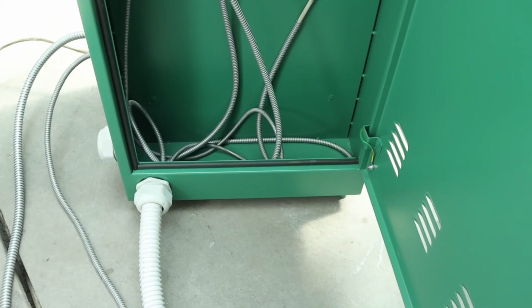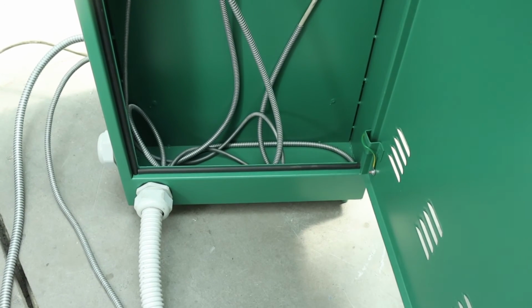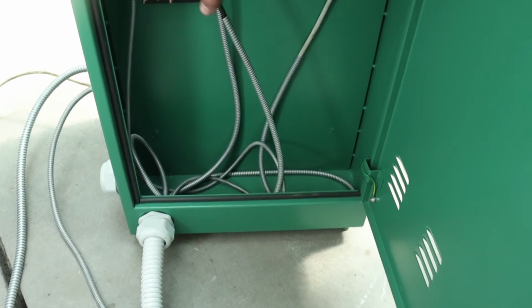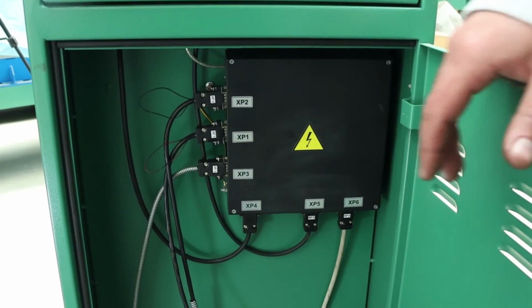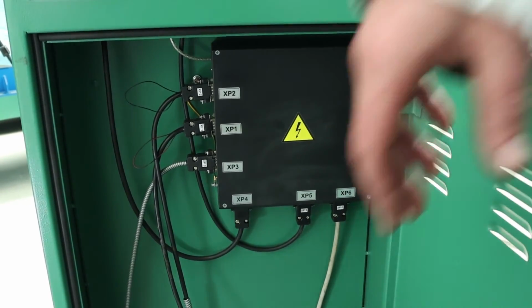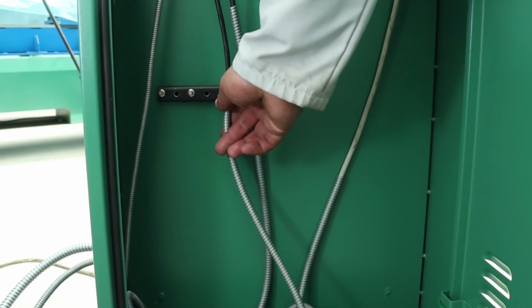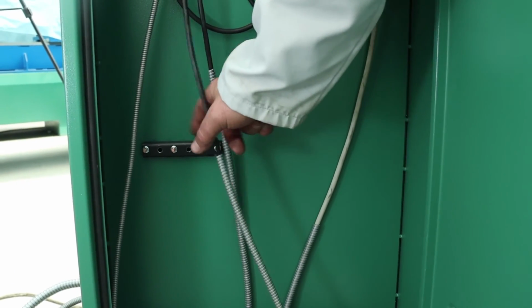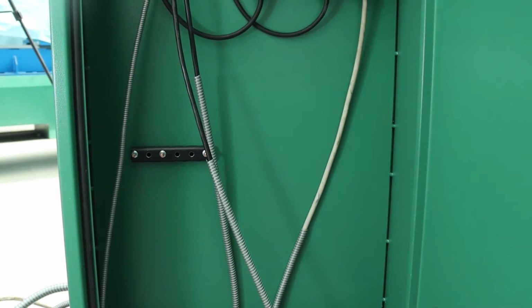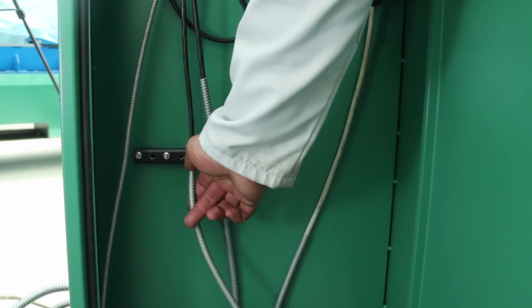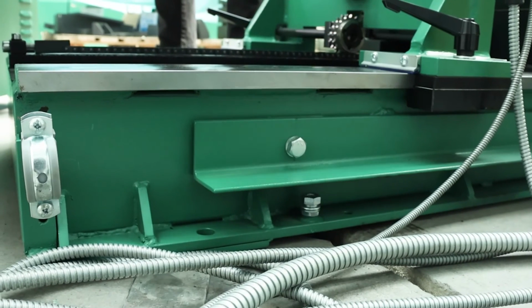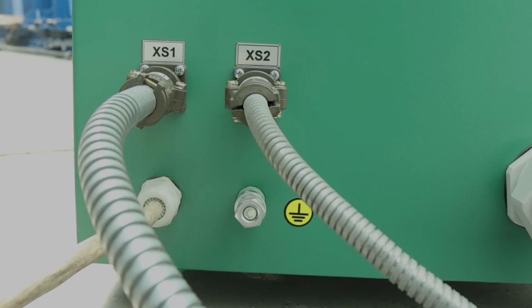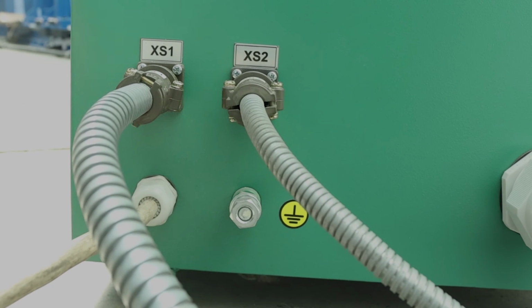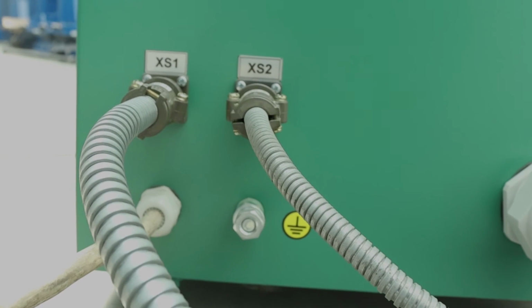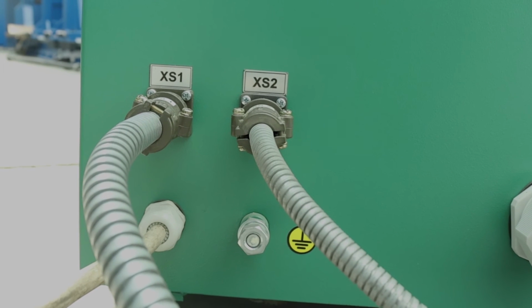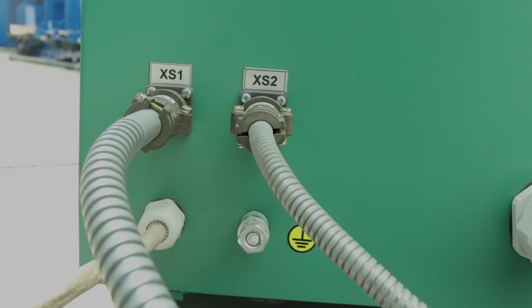The sensor cables fit to the back of the enclosure through a hole and a coupling. They are then lifted up and inserted into the appropriate connectors. All connectors are labeled. It will also be necessary to ground the metal hose using this enclosure here. So they're going to have to be placed under this comb, so that the metal duct ends at this point. This is the grounding bolt of the machine bed. The machine must be earthed. For this purpose, the grounding bolt on the electrical cabinet and the second bolt on the machine bed are used. They are grounded with different conductors to one common ground of the machine.